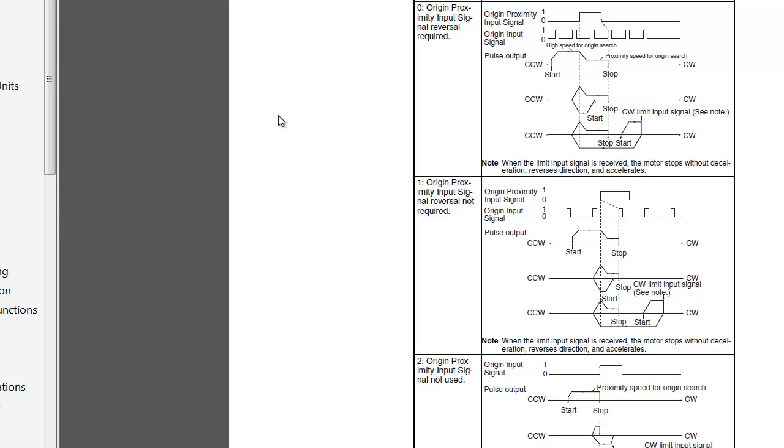which is called the origin instruction. It can be used for origin search to first establish a home or an origin return, depending on the operands that you set in it. So an origin search would establish homing after a power up to get you a known position. The origin return is just a different operand in that instruction that returns to home once you've been doing some positioning or other motion.